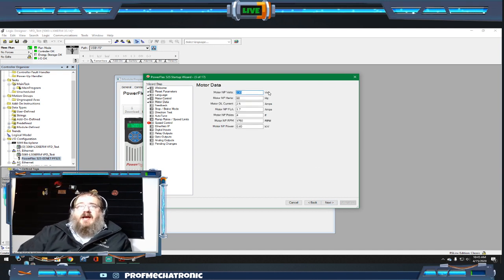We get into the next one where we actually set up the motor data. Here you can set up the number of poles, the FLA, the overload currents. All of the information for the motor itself can be set up right here in this wizard.